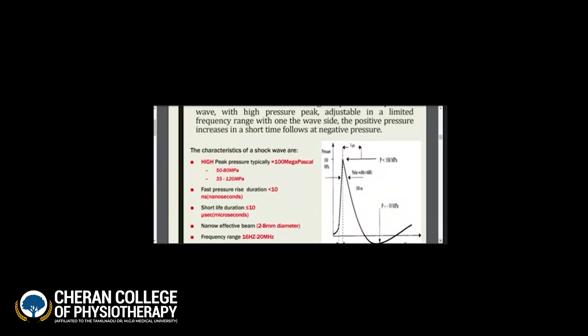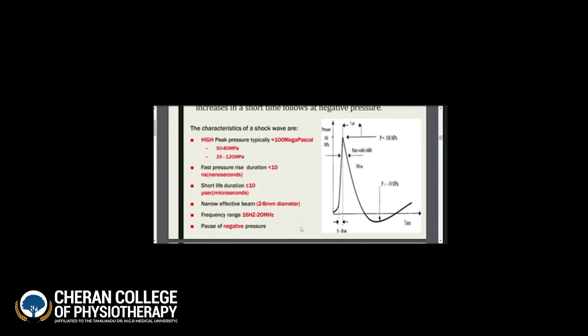Narrow effective beam, the beam shape is 2 to 8 millimeter. Frequency will be 16 to 20 megahertz. Then it will be followed by the negative pressure. You can see the graph: within 10 nanoseconds, the maximum will be 100 megapascal. So this is the physics, completely physics, of how this machine delivers to the patient.